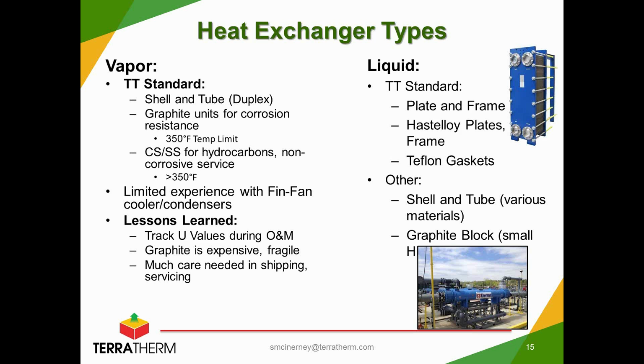We often use graphite type heat exchangers for corrosion resistance for any sites that would be potentially generating the hydrochloric and hydrofluoric acids that I talked about earlier. We go with the graphite style, whereas if non-corrosive issues or hydrocarbon type sites are what we're dealing with, then carbon steel or stainless steel type exchangers would be appropriate. And just pointing out that the graphite units, as much as they're terrific in terms of corrosion resistance, do have an upper operational limit on the vapor side of about 350 degrees Fahrenheit, which may not be sufficient for a lot of our high temperature operations, whereas the metallic type can go to much higher temperatures.